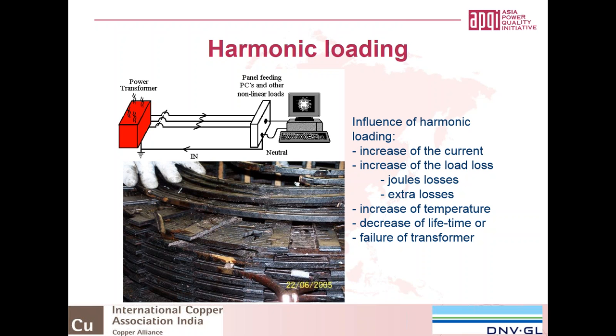That's very important. We see very often that someone is just ordering a transformer without giving those indications, and later on the transformer is used in an environment with lots of harmonic loading, and then it will definitely reduce your lifetime, or as you can see in this picture, damage your transformer, and then you have to order a new transformer, and that will take some time before you have a new transformer.